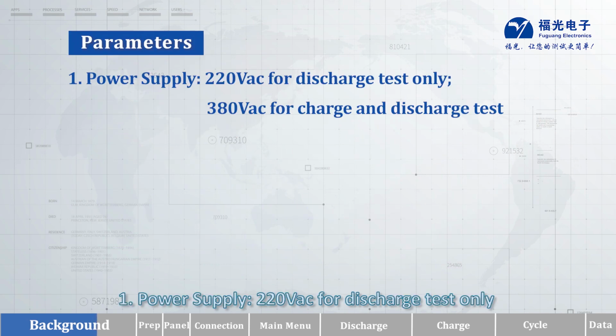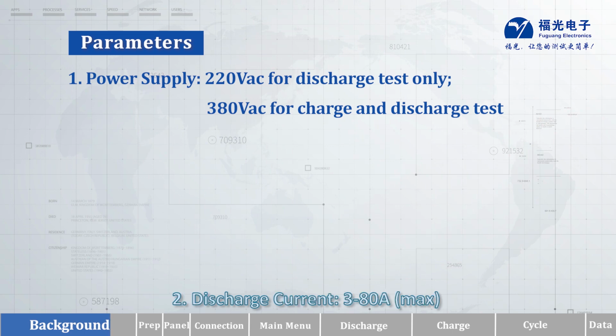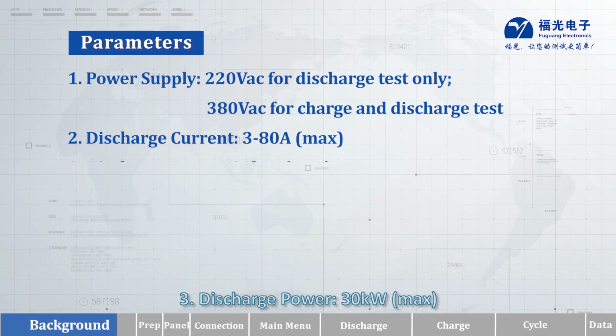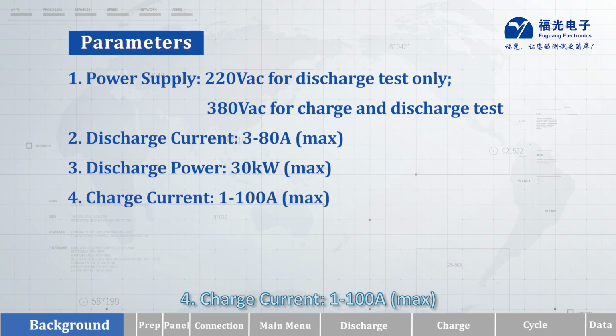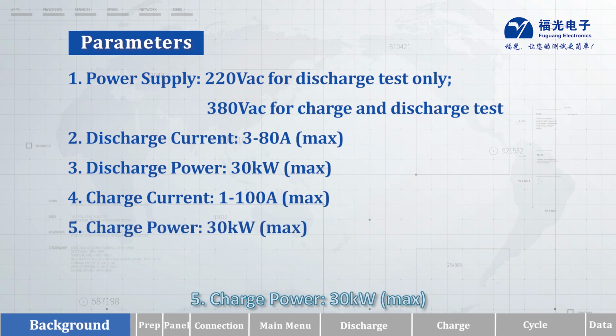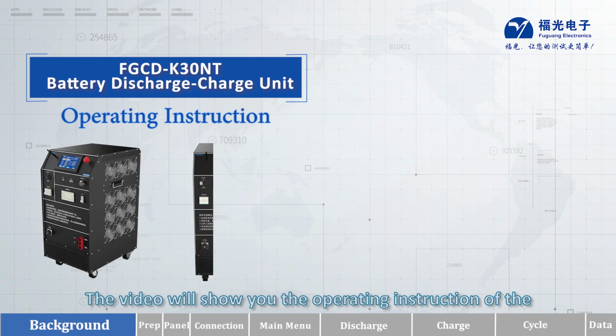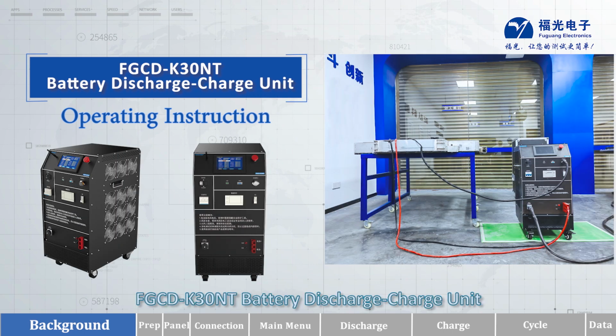Parameters. First, power supply, AC 220 volts for discharge test only, AC 380 volts for charge and discharge test. Second, discharge current, 3 to 80 amperes max. Third, discharge power, 30 kilowatts max. Fourth, charge current, 1 to 100 amperes max. Fifth, charge power, 30 kilowatts max. The video will show you the operating instruction of the FGCD-K30NT battery discharge-charge unit.